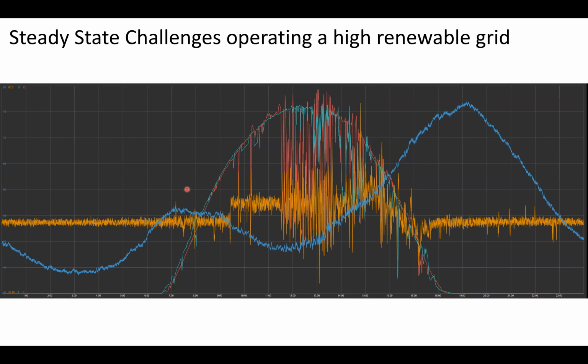So here's an event from our historian. In yellow, we have our system frequency. In blue, we have the load profile for the entire day. This is from midnight to midnight. In teal and red, we're just looking at the megawatt output of our two 12 megawatt direct to grid solar farms. And I thought this was a good slide because it shows how system frequency fluctuates as our larger direct to grid solar farms are fluctuating throughout the day.